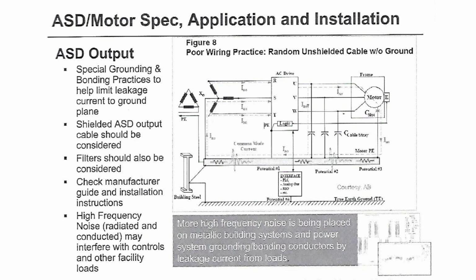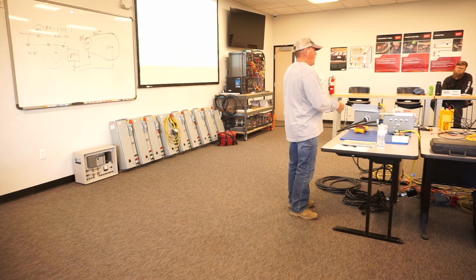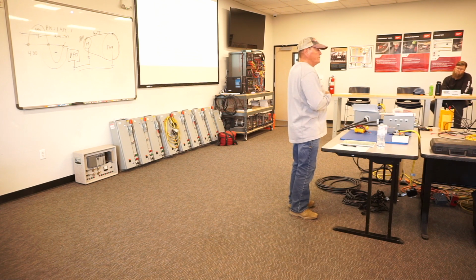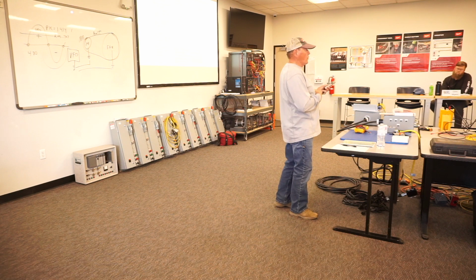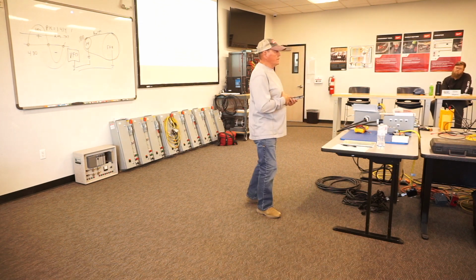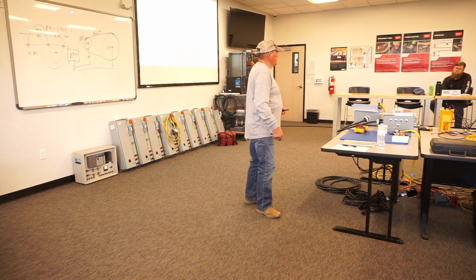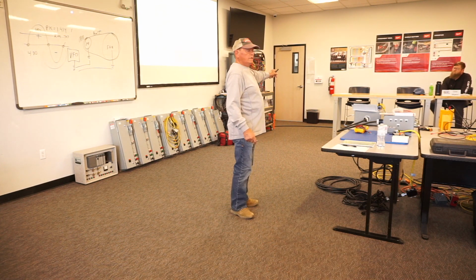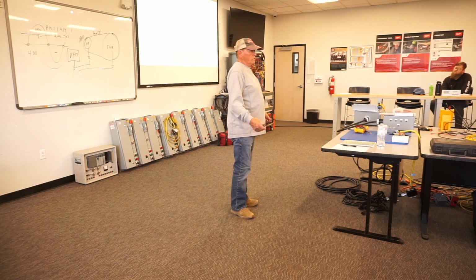So the fix is in place. Filter the output, bond the motor, and properly ground the structure of the motor. That ground has to get back to the source. The source being the drive to the switchboard to the main. One continuous path all the way to the main. Because any break in the middle of that is going to create a problem.